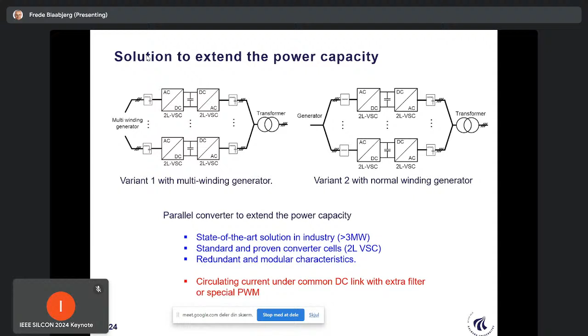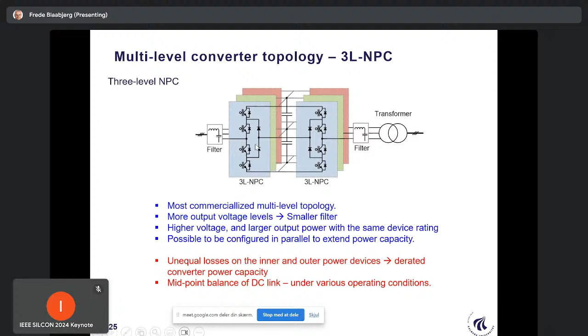However, in order to have high redundancy, there has also been a solution on the market with a multi-winding generator, for example, 9 windings instead of 3 windings. And then each converter has a connection to three phases, of course. In that way, we have double redundancy in the system. And it is seen in some solutions today. However, when we move up to very big power, 10 megawatt and above, it's natural to think about multi-level converter topologies and also higher voltages at this stage, maybe 3 kilovolt, 3.3 kilovolt or something like that. We are seeing that, and in that case, the 3-level neutral point clamp converter is of interest.